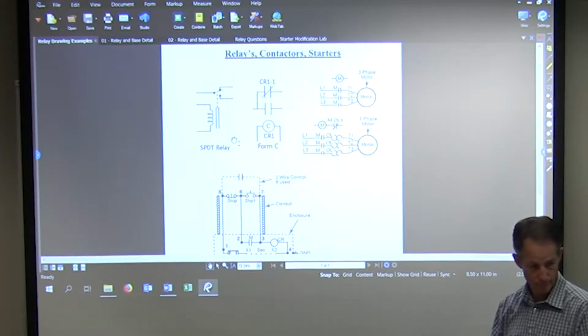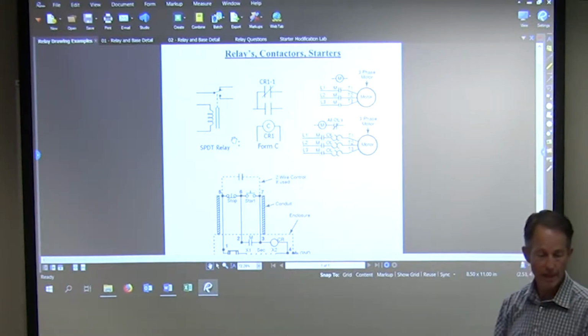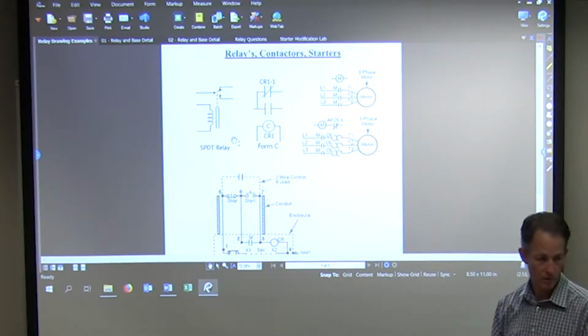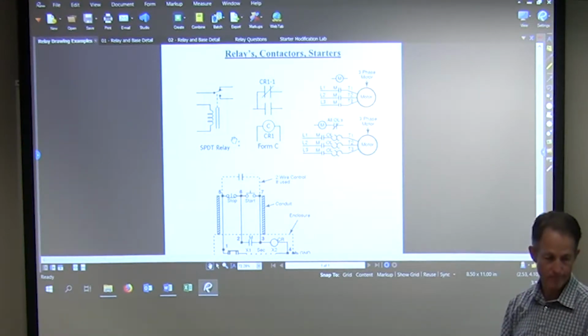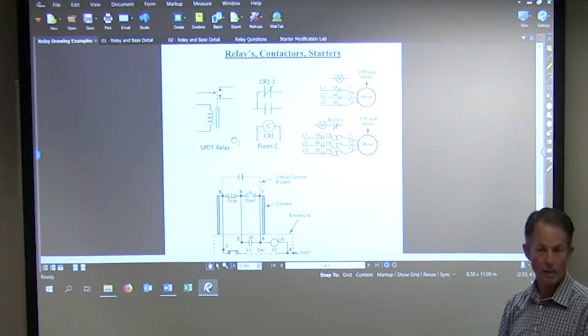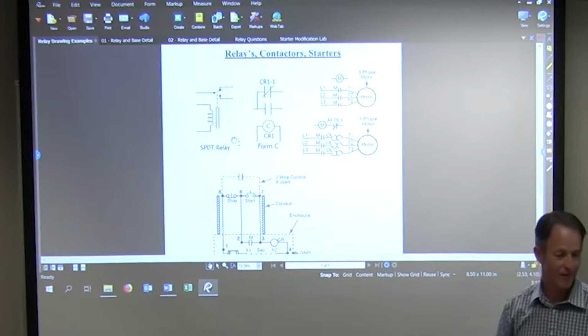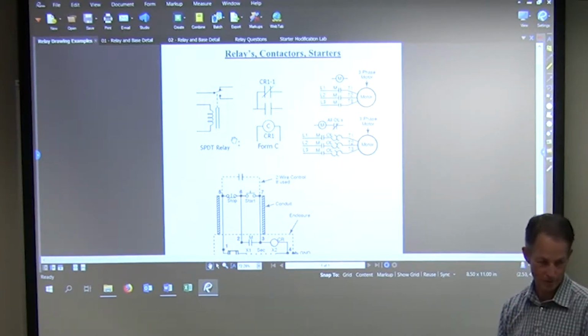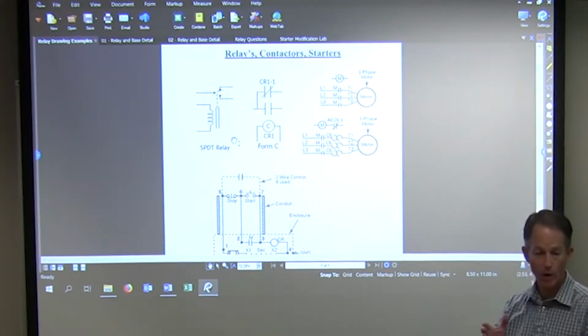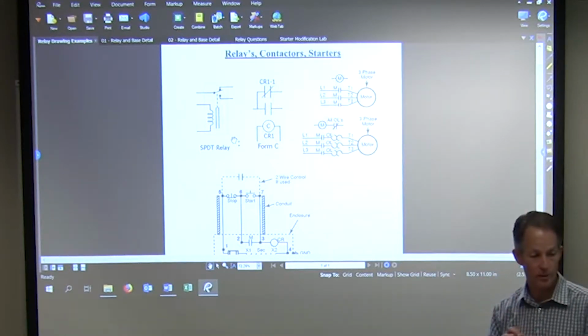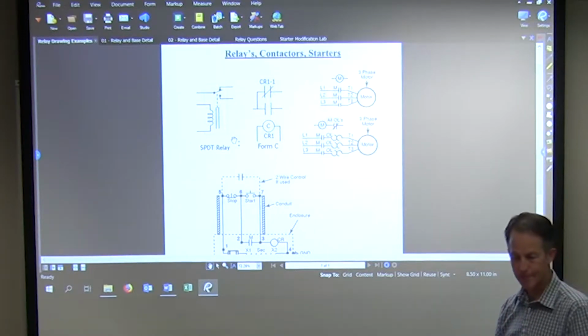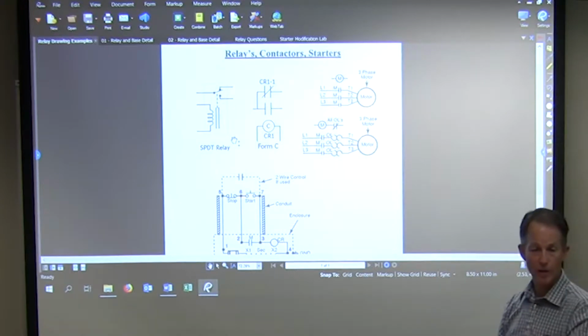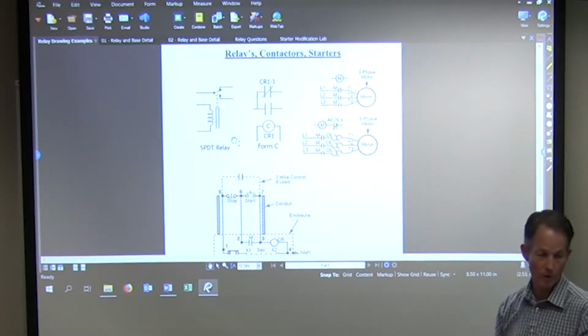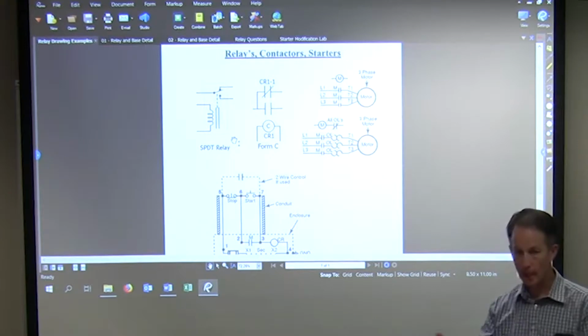If the coil is open, then won't your meter still pick up 24 volts because you've got potential? That'd be a difference of potential. You would, because you're going across. You're bridging it. If you're going across the coil and the coil is open, you'll still get 24 volts. So that's not a very good way to test a coil. You will see if you've got voltage there, and that's about it. You won't necessarily know if the coil's pulled in. True. So if the coil has burned up and has an open in the circuit, you would also see 24 volts there. But either way, you at least verify that you've got voltage there, and then it's a matter of whether the voltage matches the rating of that coil. So, okay. Contacts, how do we troubleshoot contacts?